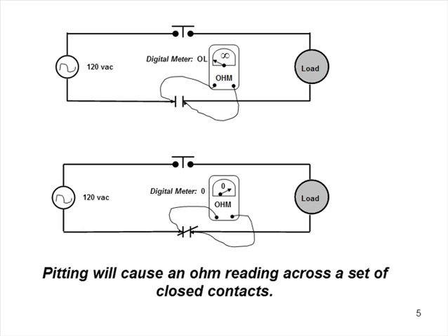Every time that happens, if you read the box, the paperwork, the contactor comes in, it'll tell you how many duty cycles it's good for, 2,000, 20,000, whatever the case is, depending on how good the contacts are. And what that means is that's how many times it can open and close before pitting starts, and you start to get a voltage drop or a resistance drop across it. If you have 1 volt drop or a 1 ohm drop, I'll say, across that contactor, replace it, because it may be running now, but it's on its way out.